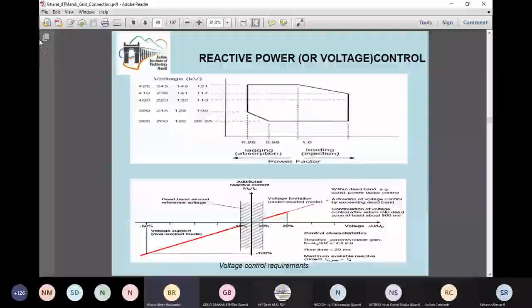If the voltage is reduced by 50%, then 1 per unit of additional reactive current is expected to be required. It means that if the grid voltage is reduced, reactive power needs to be fed into the grid due to this reduction. For 50% voltage, it is given as 1 per unit, meaning the rating of the machine itself. So this becomes a very strict grid code, which is from the German grid code. Right? Next slide, please.